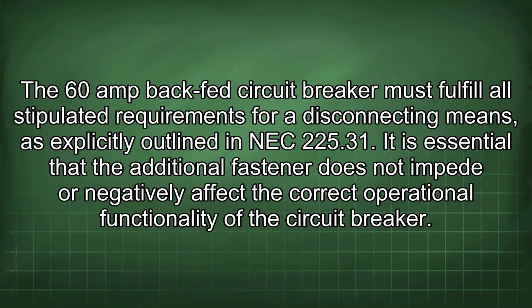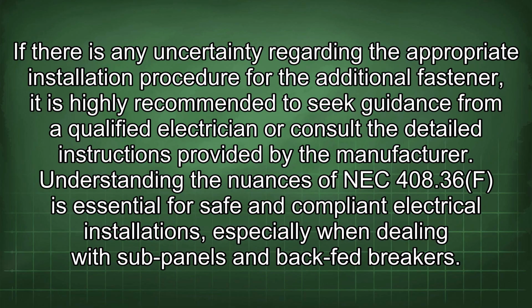The 60-amp backfed circuit breaker must fulfill all stipulated requirements for disconnecting means, as explicitly outlined in NEC 408.36. It is essential that the additional fastener does not impede or negatively affect the correct operational functionality of the circuit breaker. If there is any uncertainty regarding the appropriate installation procedure for the additional fastener, it is highly recommended to seek guidance from a qualified electrician or consult the detailed instructions provided by the manufacturer.